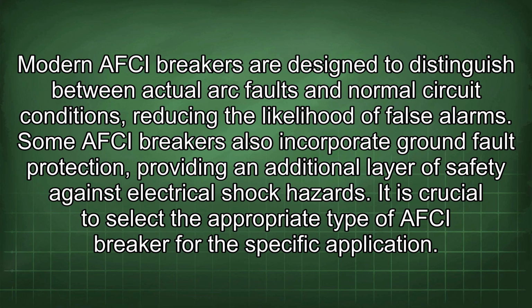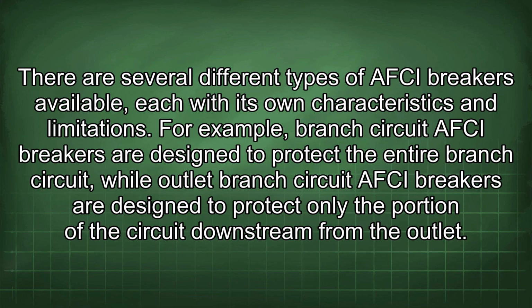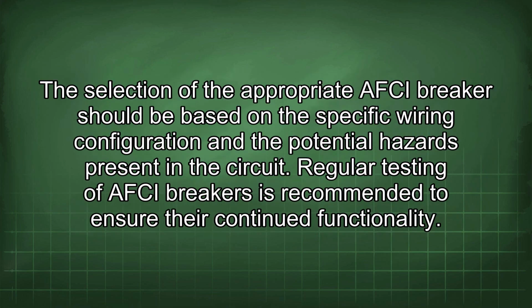It is crucial to select the appropriate type of AFCI breaker for the specific application. There are several different types of AFCI breakers available, each with its own characteristics and limitations. For example, branch circuit AFCI breakers are designed to protect the entire branch circuit, while outlet branch circuit AFCI breakers are designed to protect only the portion of the circuit downstream from the outlet. The selection of the appropriate AFCI breaker should be based on the specific wiring configuration and the potential hazards present in the circuit. Regular testing of AFCI breakers is recommended to ensure their continued functionality.